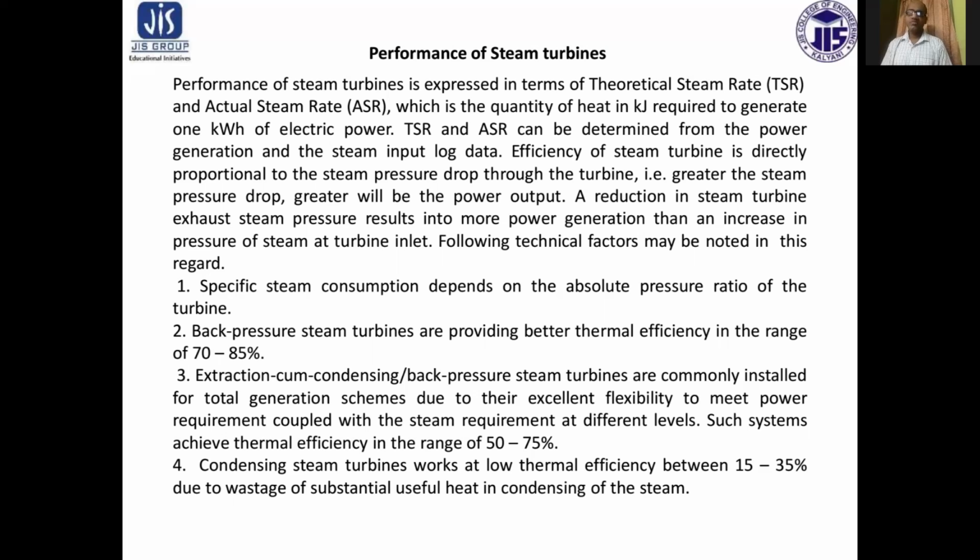Efficiency of a steam turbine is directly proportional to the steam pressure drop through the turbine. That is, the greater the steam pressure drop, the greater will be the power output. A reduction in steam turbine exhaust steam pressure results in more power generation than an increase in pressure of steam at turbine inlet.